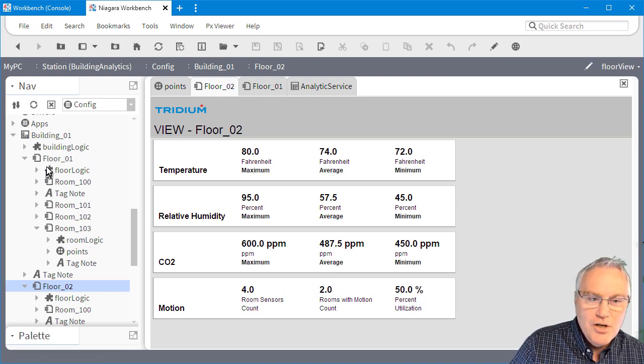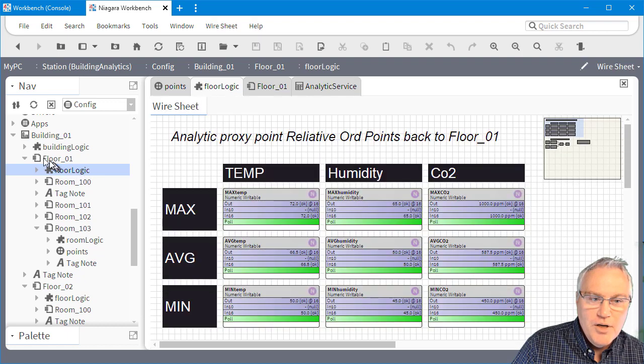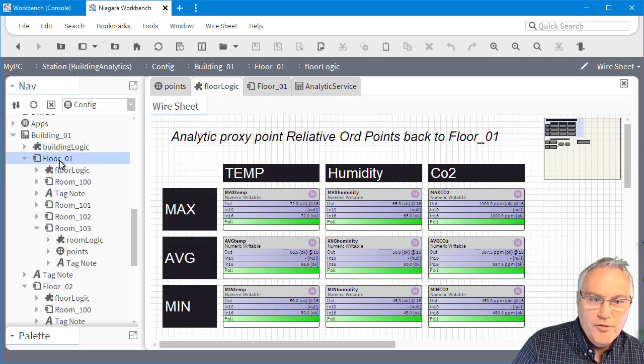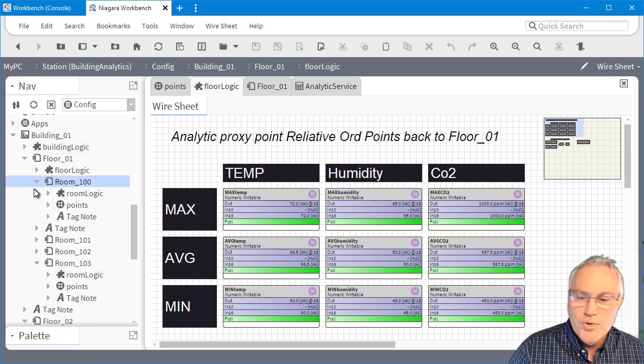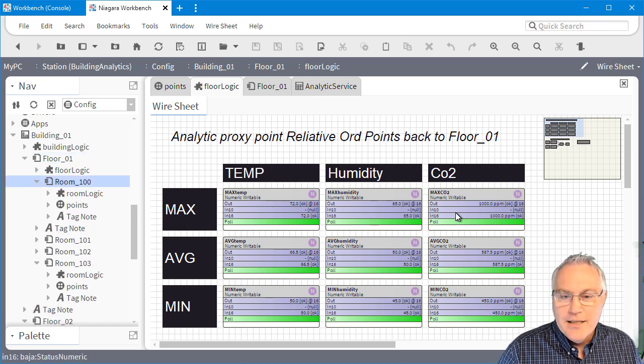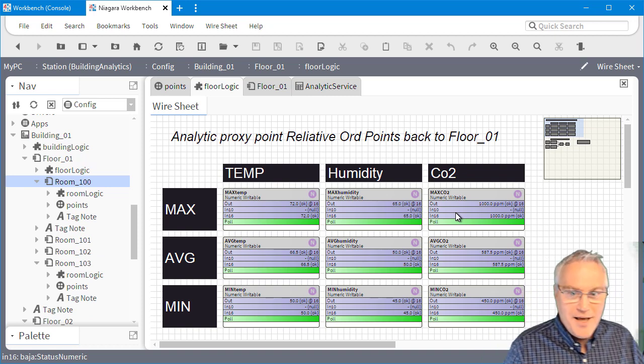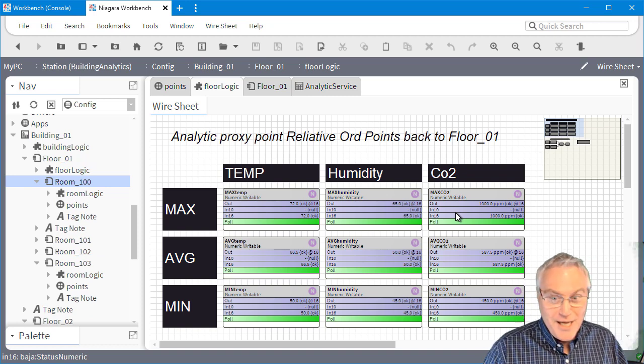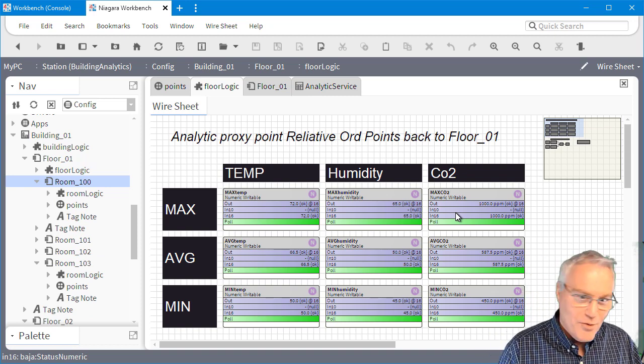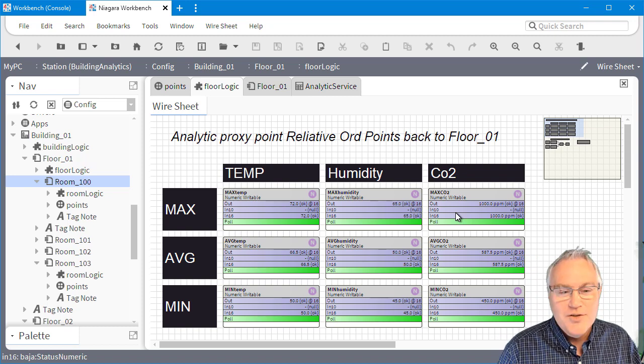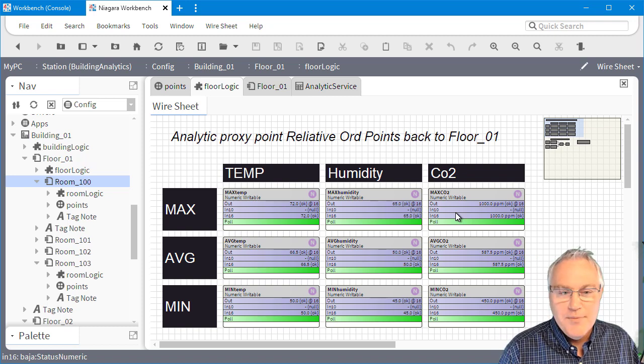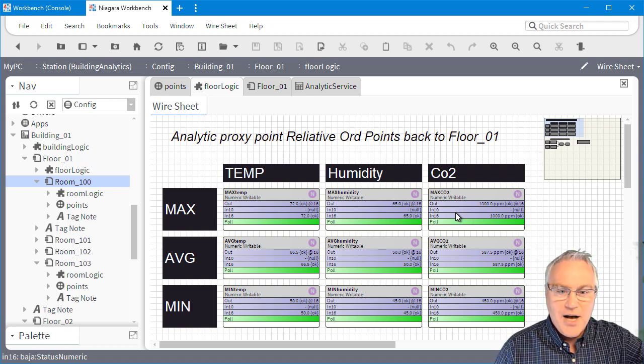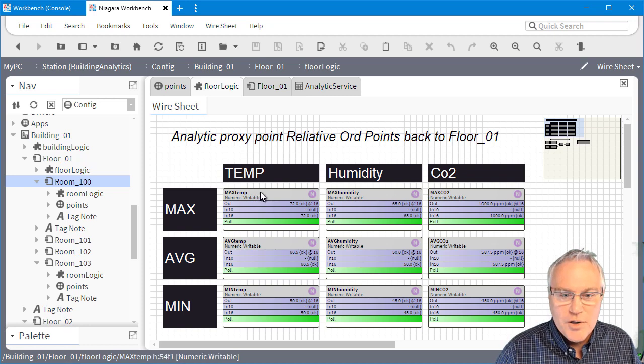Each calculation from the floor logic folder is executing either on the building, on the floor, or on the room level. And so that's how you do analytics. And this is all real time. I didn't even have any history files. You add history files and then you can have the fun of saying what was the average temperature last week. So this is just saying real time data.